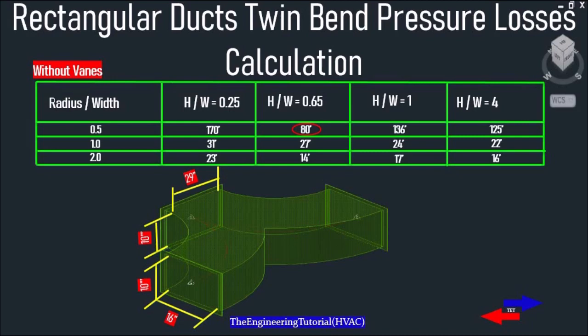Dynamic losses occur due to flow across fittings such as elbows, offsets, takeoffs, and any restrictions, or whenever the airstream makes turns, diverges, narrows, widens, enters, or passes through fans, dampers, gates, coils, and filters. Friction and turbulent flow play a big role, so before designing and installing ducts we have to understand these steps.